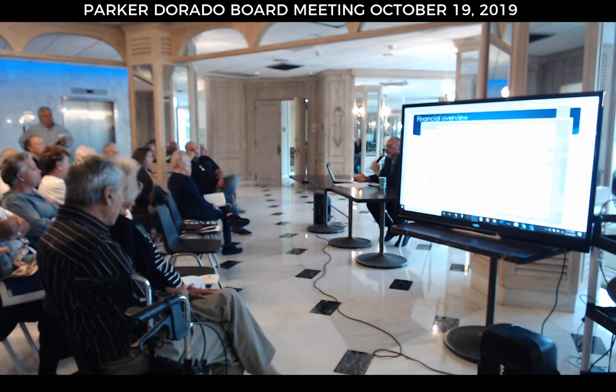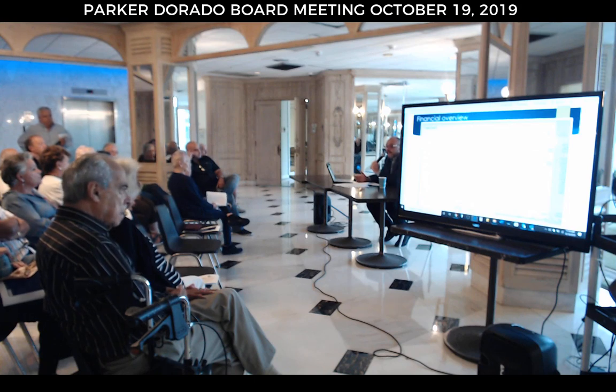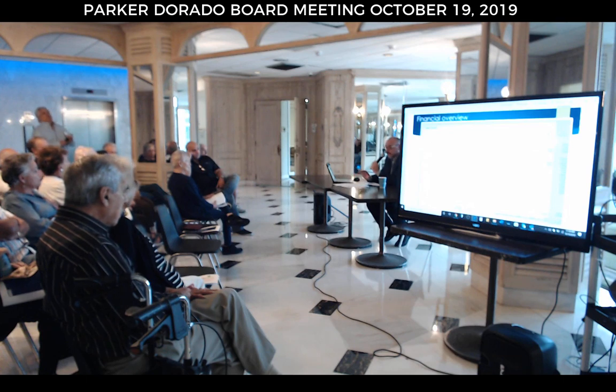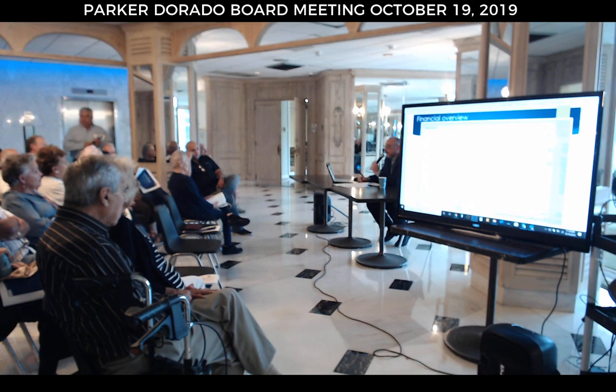We went through a hurricane. They put everything on emergency status and would not even talk to us about a maintenance issue until now. We had communication with them on Thursday, and they're saying they're setting up within the next two weeks for us to come in and do service on the switchgear. Again, this is something that has been neglected on this building for at least 10 years - that's all they go back and record, is 10 years. So you've neglected something that is virtually running everything in this building.